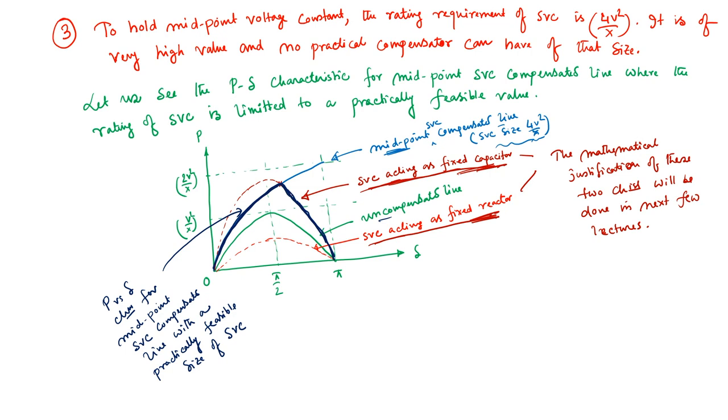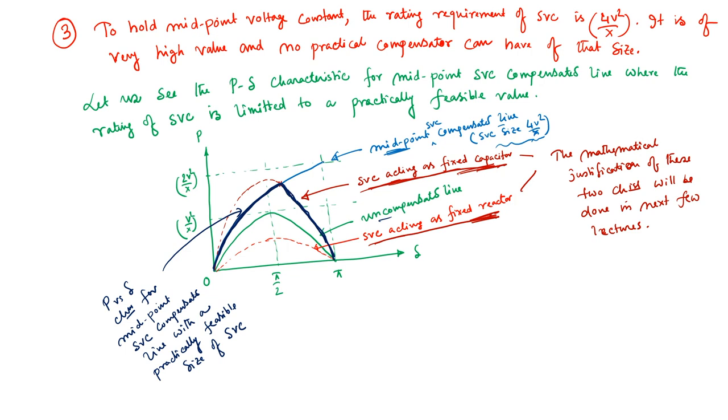And this illustrates that for a practically feasible size of the SVC for an SVC compensated line, the characteristics would not be as it was for the theoretically maximum power limit of the midpoint compensated SVC line with SVC size 4 V square by X. So, it will not be following this blue characteristics ever, but it will be this black characteristics when the size is limited to a practically feasible value.